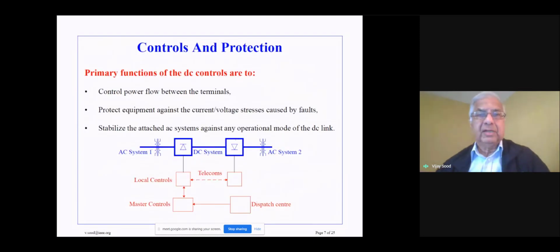The functions of the HVDC controls are as follows. Their primary objective is to control the power flow between the two terminals, the two DC terminals. They also must protect the equipment against any current or voltage stresses caused by any faults.